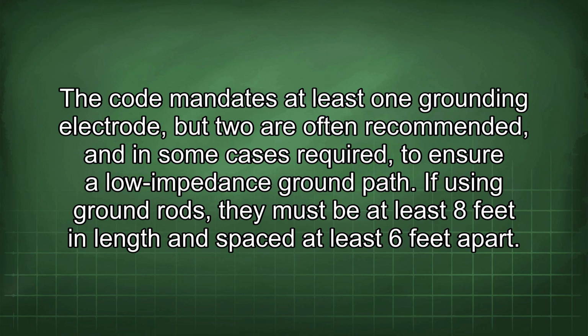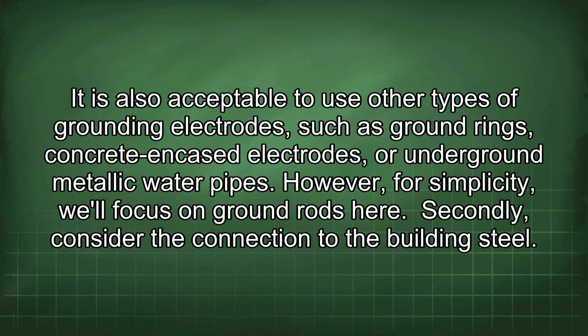If using ground rods, they must be at least 8 feet in length and spaced at least 6 feet apart. It is also acceptable to use other types of grounding electrodes, such as ground rings, concrete encased electrodes, or underground metallic water pipes. However, for simplicity, we'll focus on ground rods here.